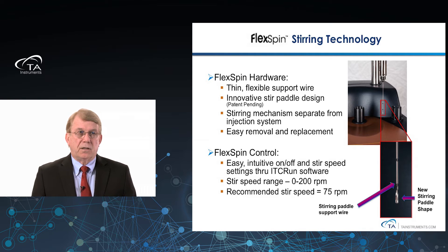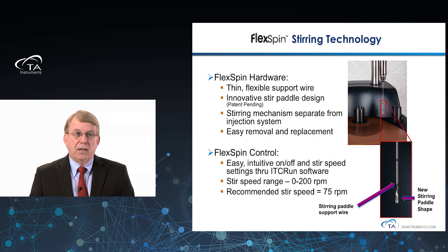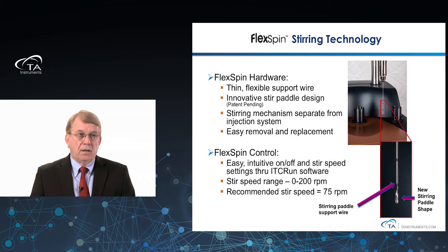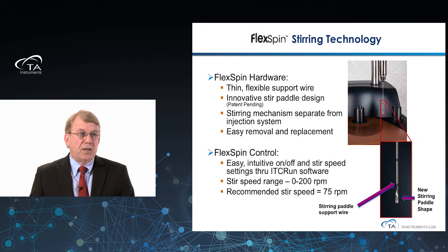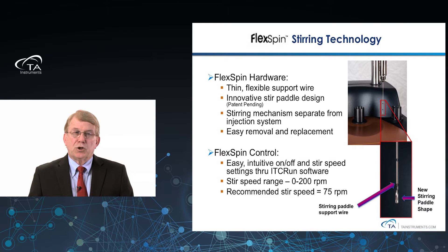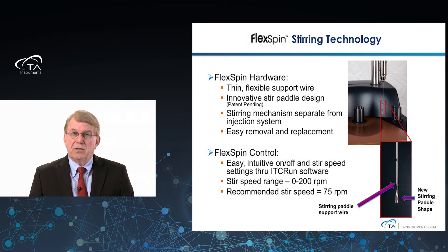Flex-spin stirring — what is it? You have a very thin flexible support wire that comes down and supports an innovative stir paddle design. As you see in the inset, it is separate from the injection cannula that comes down right beside it. The flex-spin control is programmable; the on/off and stir speeds are controlled from ITC Run. The stir speed range is from about 0 to 200 RPM with a recommended stir speed of 75 RPM, so that sensitive or fragile proteins are not damaged by excess stir speeds during the ITC titration.